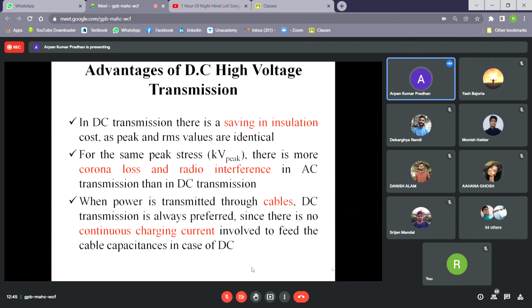I have already informed you that whether we consider an AC or DC system, the insulation design depends on the peak value of the voltage signal. That means for an AC signal, you have to consider its peak value. For a DC system, since there is no such concept, you can design the insulation system based on that magnitude directly. But for an AC system, since the RMS value and peak value are not equal, and the peak value is higher than the RMS value, you have to design the insulation system based on the peak value. So the insulation cost will be higher.